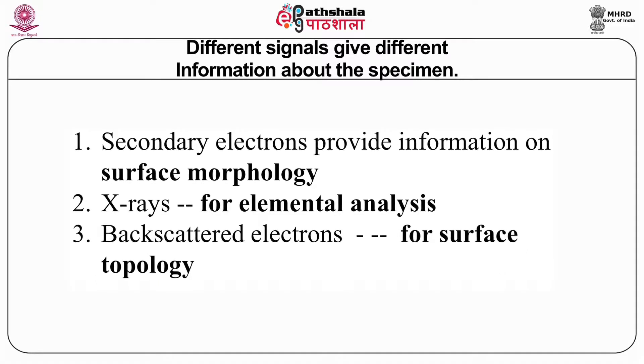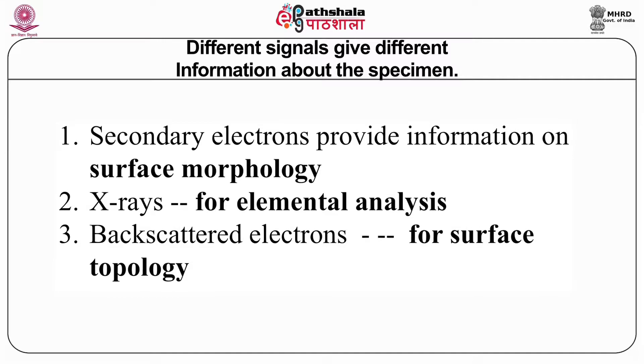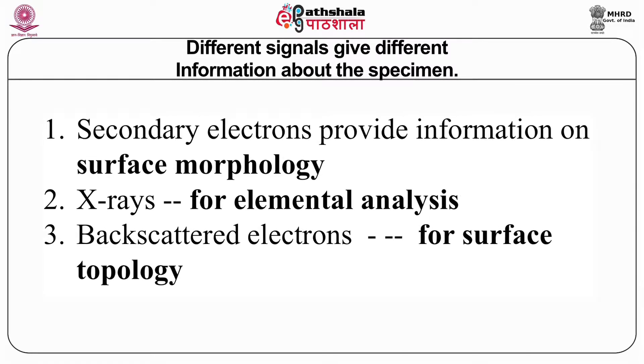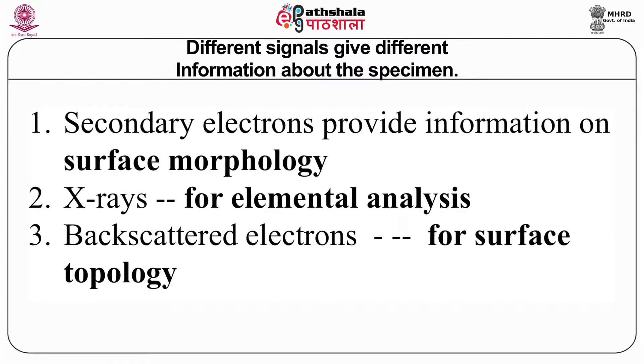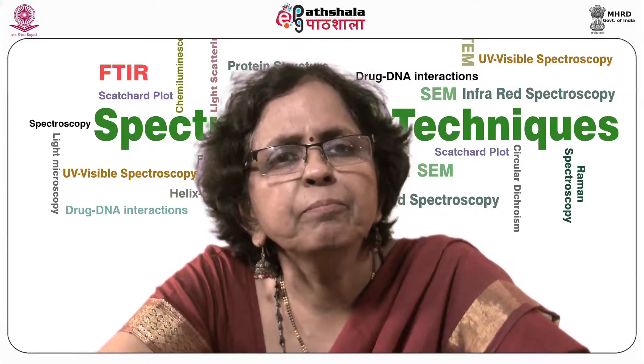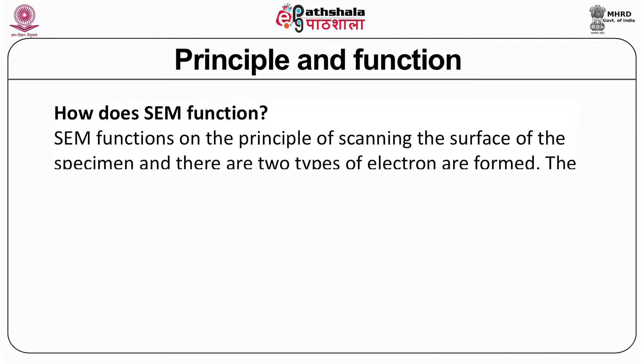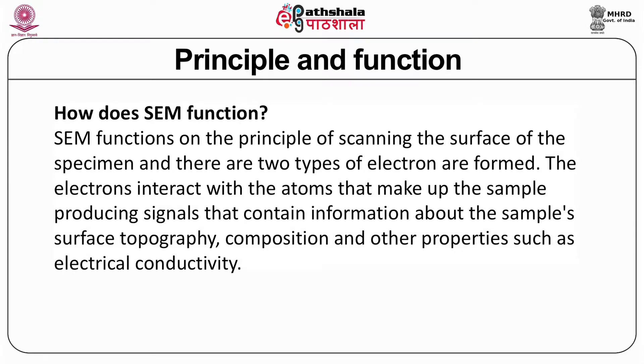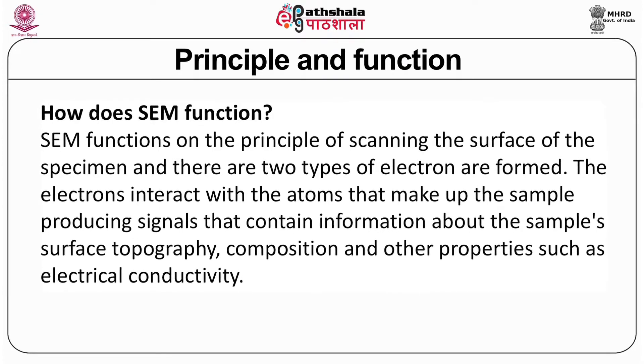The different signals give different information. Secondary electrons give surface morphology as in SEM. X-rays can be used for elemental analysis, which I will cover at the end after studying the whole SEM. Backscattered electrons also give surface topology in more detail — not a 2D but a 3D picture. The SEM functions on the principle of scanning the surface of the specimen; electrons interact with the atoms making up the sample to produce signals that give information about the sample's surface topography, composition, and properties such as electrical conductivity.